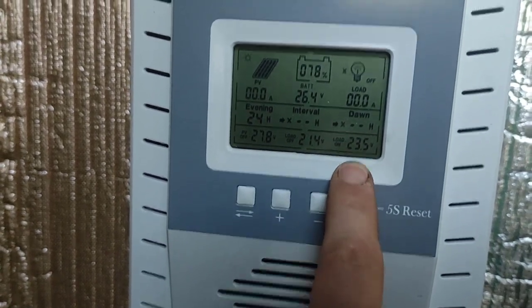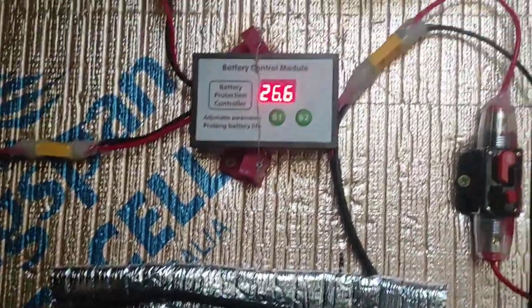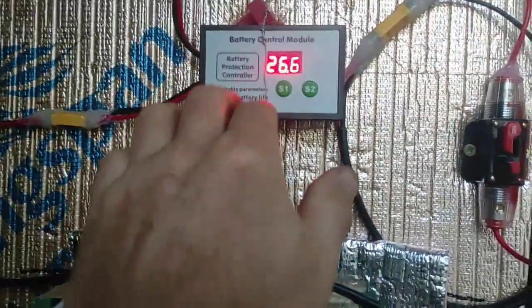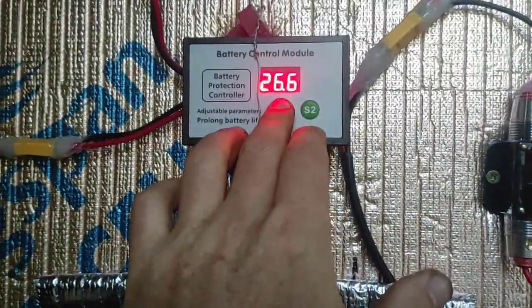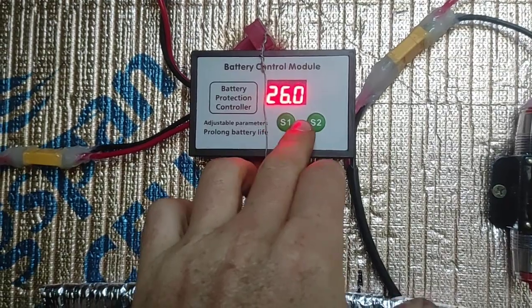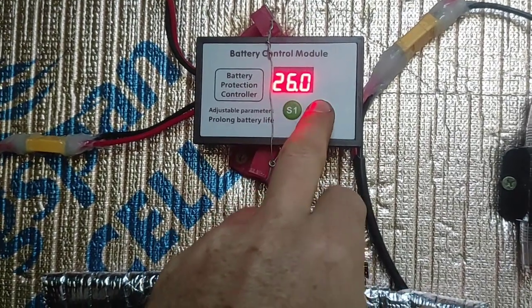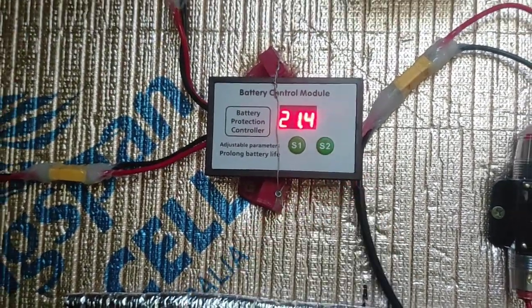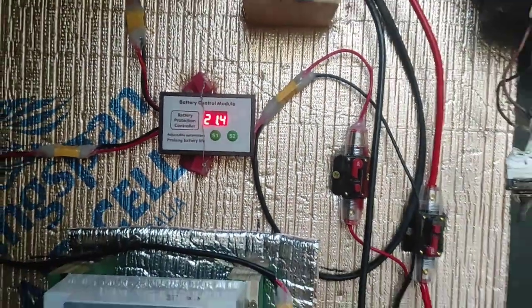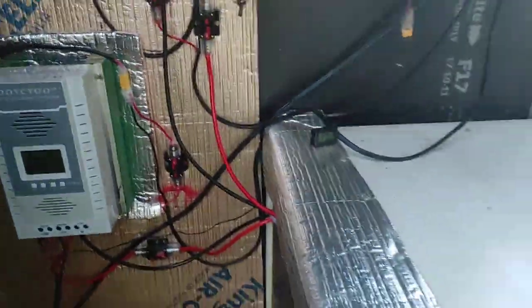Here it's 23.5. Well, this thing up here does the exact same thing. Here I've got the high voltage set at 26, so it'll turn back on at 26. And here, if it ever gets as low as 21.4, it'll cut off rather than relying on the BMS system.